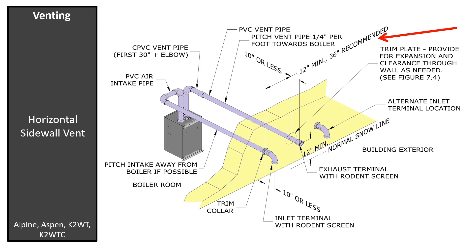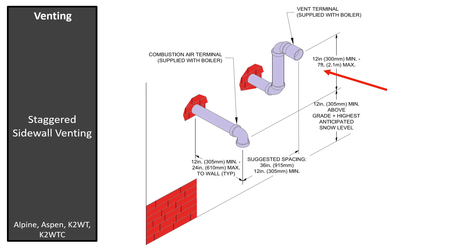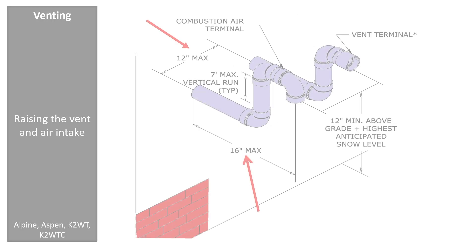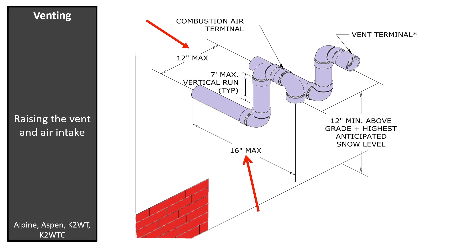The distance from the wall will exceed the maximum distance from the exterior wall of the structure. Another option to obtain greater separation to avoid cross-contamination while maintaining 12-inch minimum between the pipes is to raise the vent termination up to a maximum of 7 feet vertically above the air intake exterior of the structure. Both terminations may be installed with a vertical maximum rise of 7 feet outside. Be cognizant of the distance between the pipes when exiting the wall, as it may be different depending on the venting option used. In this application, the maximum distance from the center line of the pipes is 12 inches, but in a two-pipe through-the-sidewall application the distance was not limited to 12 inches.